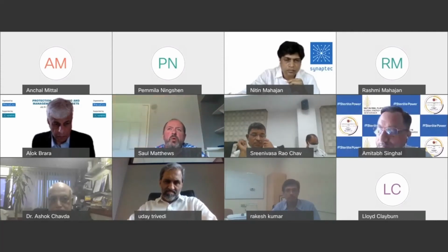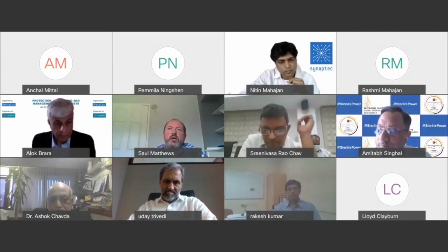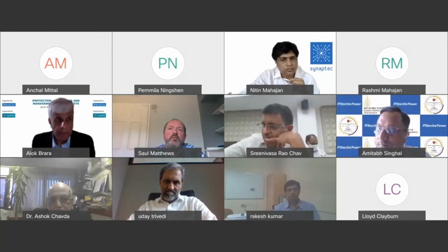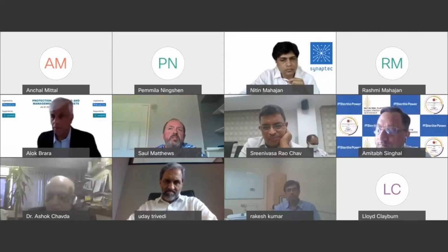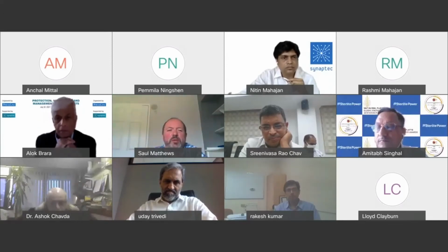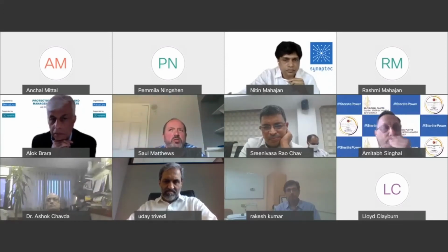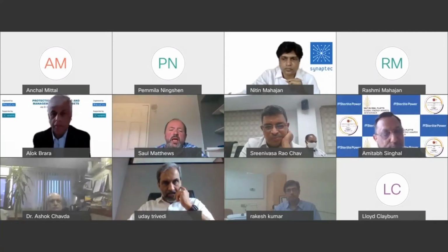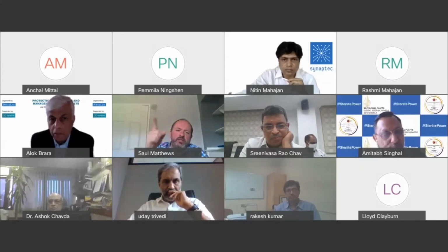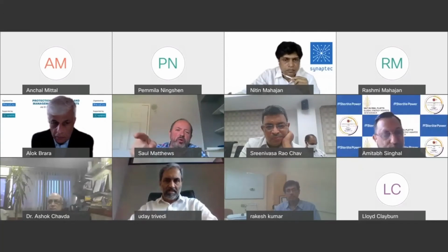We can look at those 50 things, and if one of them shows a different profile, electrically or physically, mechanically, and the other 49 all look the same in that sample set, then it makes sense to use our system to automate condition monitoring, because we can simply say, hey, there's this location over here, something is behaving differently, all the others are the same, so go and visit that one because something's wrong, not because it's Friday afternoon and that's the time to go and do it.